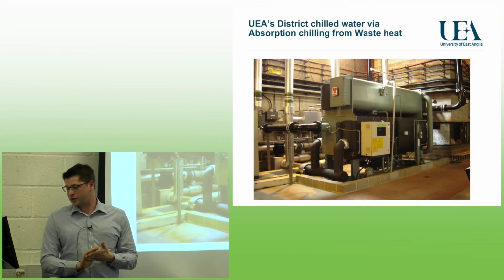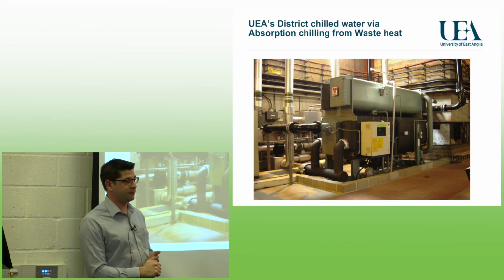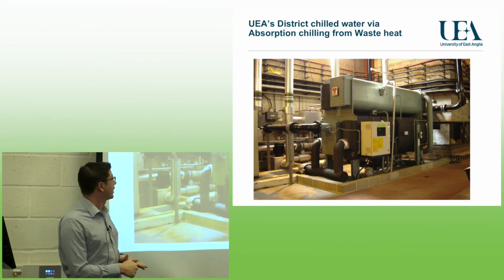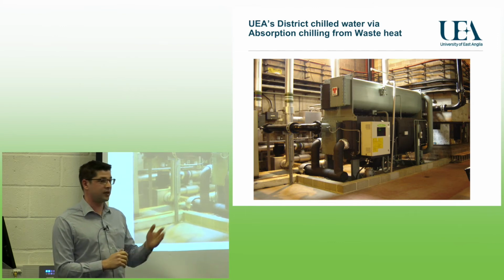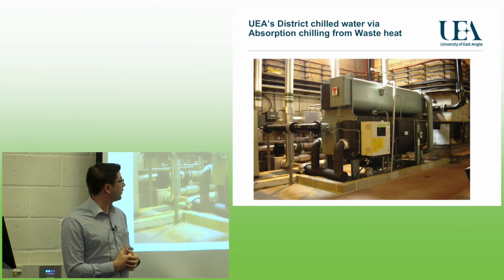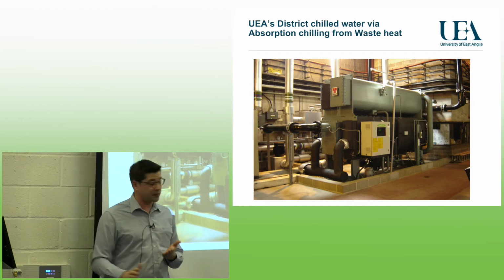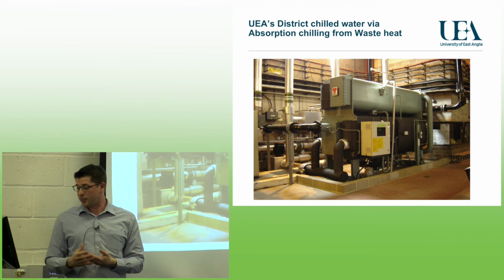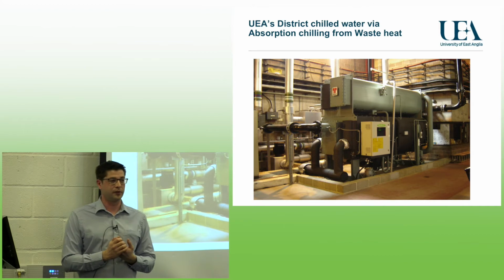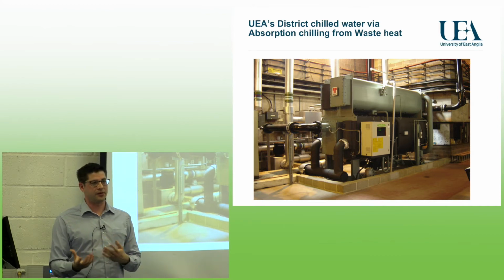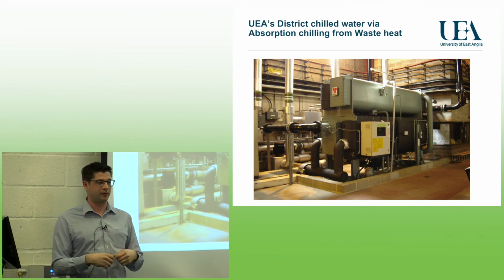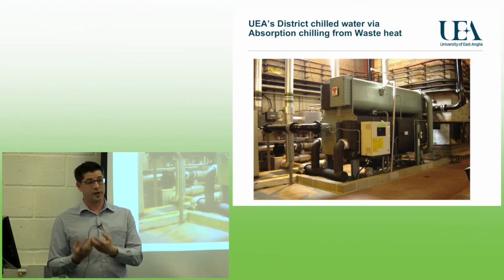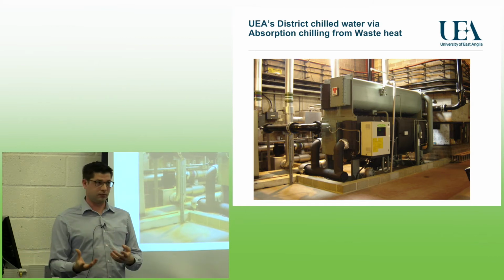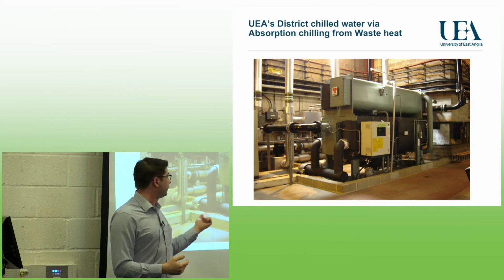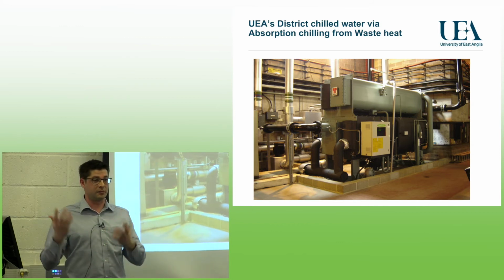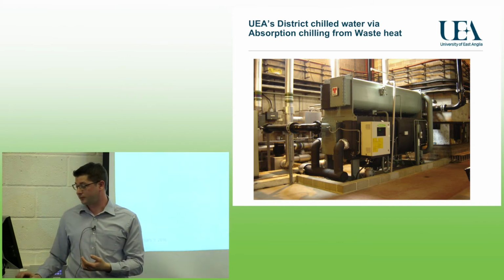And this is our absorption chiller. This uses waste heat from the engines in the summer to produce cooling across the campus. We've got a district cooling system which runs down the teaching wall to the Sainsbury's Centre. Quite a useful piece of technology. It's not particularly efficient - an electric chiller has a COP, which is the power to heat ratio, of about 3.5. So for every kilowatt hour of electricity you put in, you get 3.5 kilowatt hours of cooling out. This is only 0.7, which seems a bit silly, but if we weren't using the heat in that, we would be rejecting it to the atmosphere so we could run the engine. So it's just using waste heat.